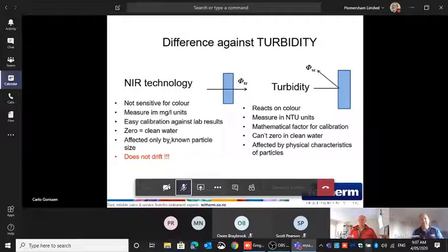What's the main difference against turbidity? Well, first of all, we don't see color. So if you got water or you got tea, for instance, if we put our sensor in tea, it will come up with zero. You put a turbidity sensor in tea and it just goes nuts. That's the big difference with our sensors. So for dairy people, if you want to see color, if you want to see milk escaping or something, we can't see that. We only see solids.